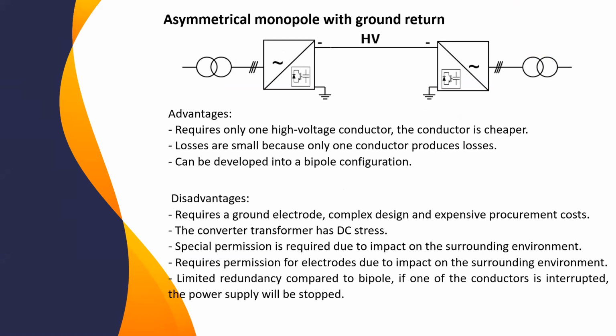Let me try to clarify. For asymmetrical monopole, we have two types. One with ground return, where we only have one high voltage conductor and no second conductor, using ground instead. But the problem with ground return current is that sometimes when it passes near metallic equipment or an AC substation, it can disturb the AC substation or cause corrosion of metallic parts.